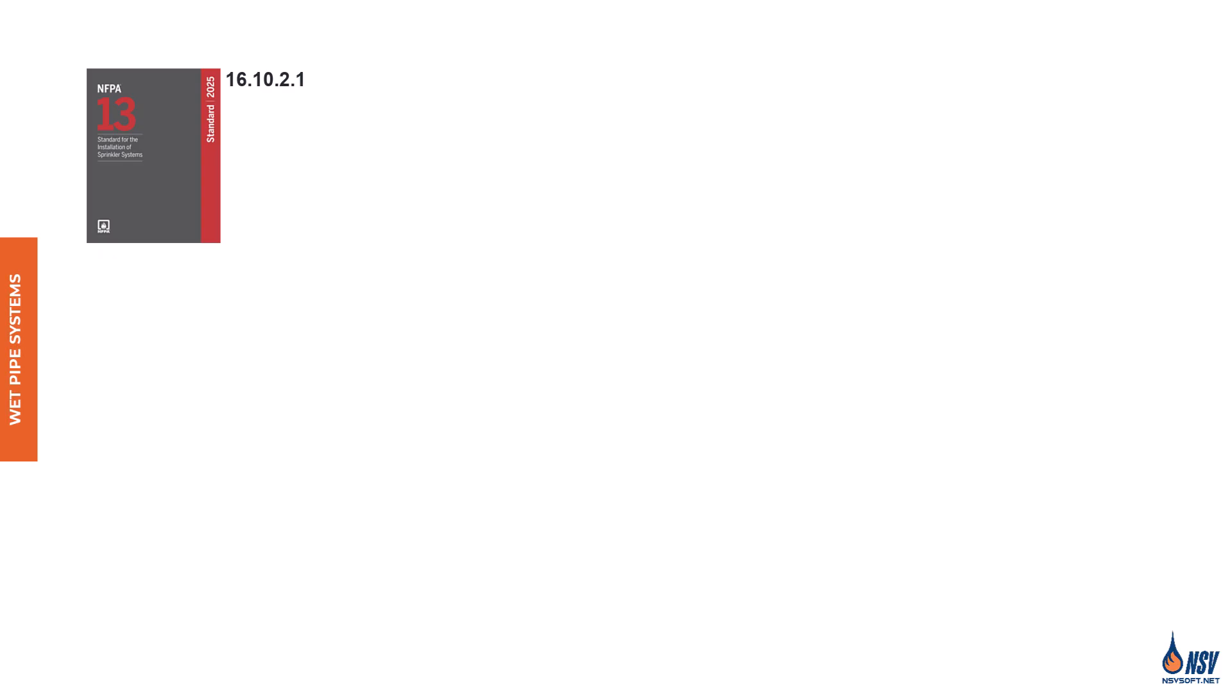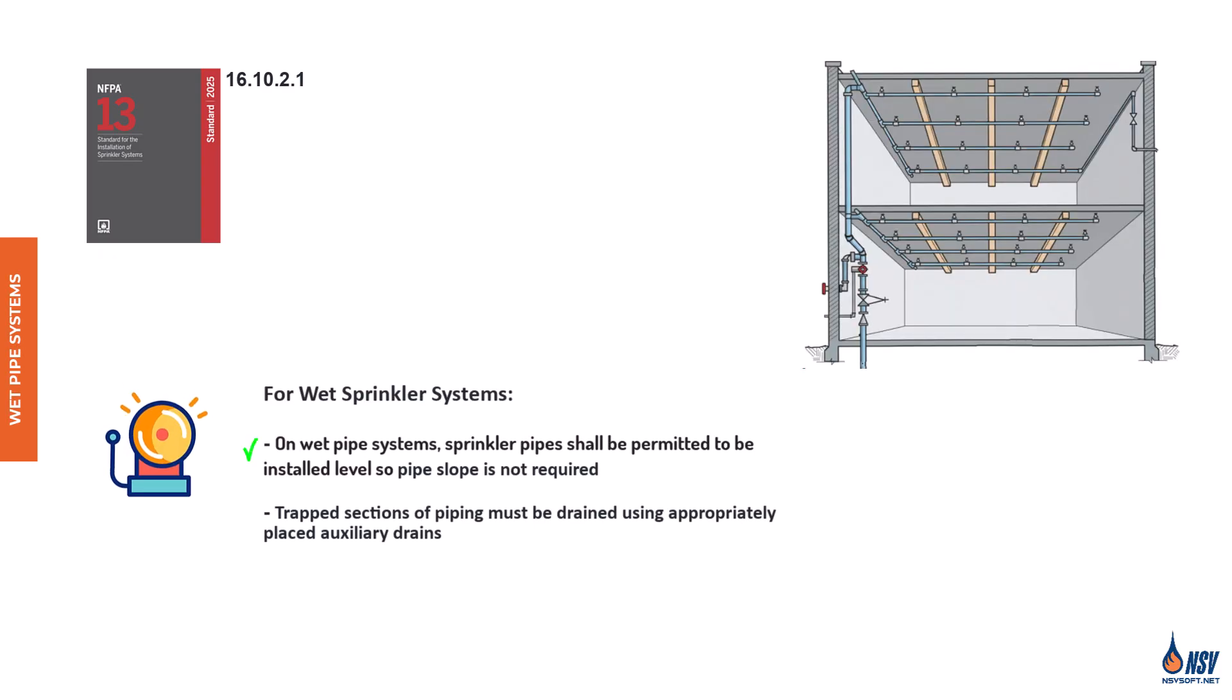According to Section 16.10.2.1, in wet pipe sprinkler systems, NFPA 13 permits the piping to be installed level. In pipe schedule systems, the gradual reduction in pipe size from the supply to the branch lines naturally creates a slight pitch, even when the pipes are installed level. This is due to the slope of the reducing fittings. However, in hydraulically calculated systems, especially those with looped or gridded configurations, this natural pitch is less pronounced. Still, when installed level, most of the water will drain out of the piping, and because wet systems are typically installed in areas not subject to freezing, small amounts of residual water are not considered problematic.